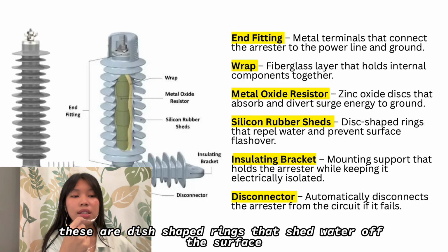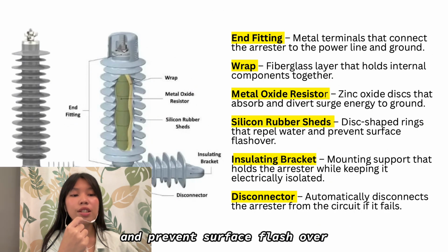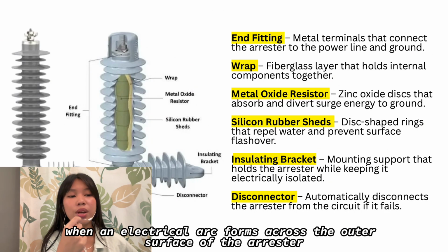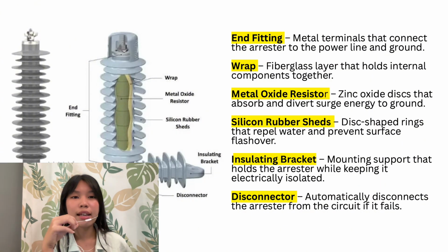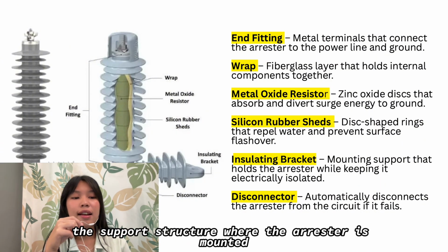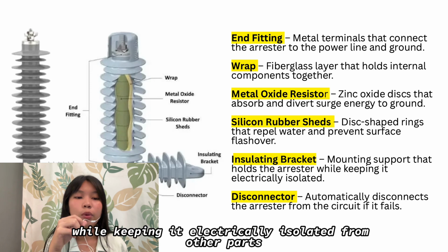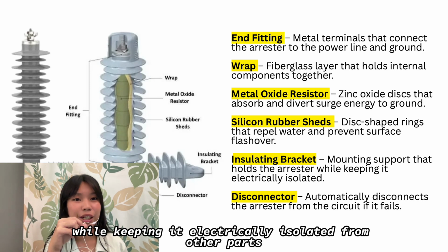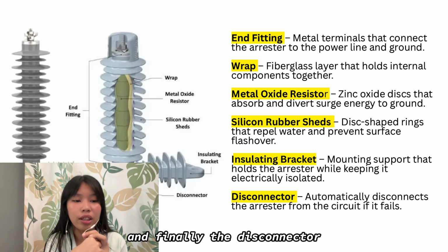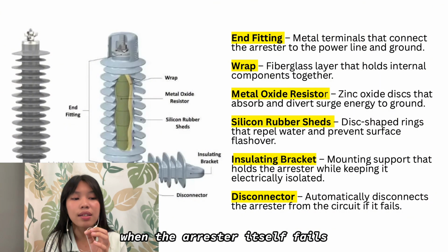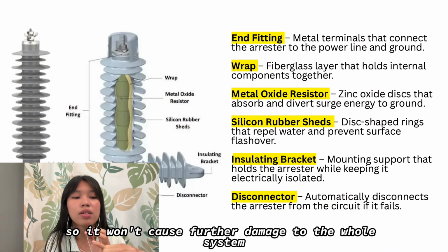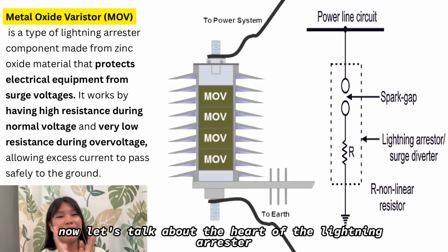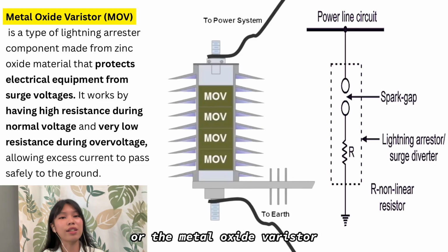These are disc-shaped rings that shed water off the surface and prevent surface flashover when an electrical arc forms across the outer surface of the arrestor. Fifth is the insulating bracket, the support structure where the arrestor is mounted while keeping it electrically isolated from other parts. And finally, the disconnector. When the arrestor itself fails, it automatically disconnects from the circuit so it won't cause further damage to the whole system.